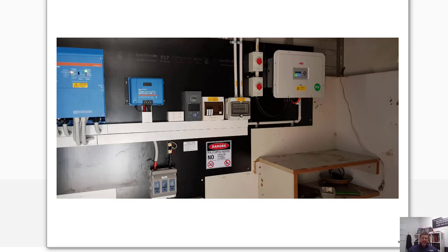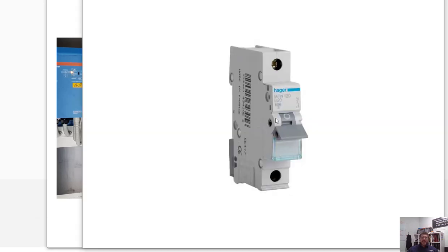When there are complications with this little circuit breaker, customers who have installed a solar system call and say Mike, I've got no power. They go out and flick the circuit breaker. What that means when the circuit breaker trips is that the customers have turned on a load too big for the inverter — the breaker is there to protect the inverter.